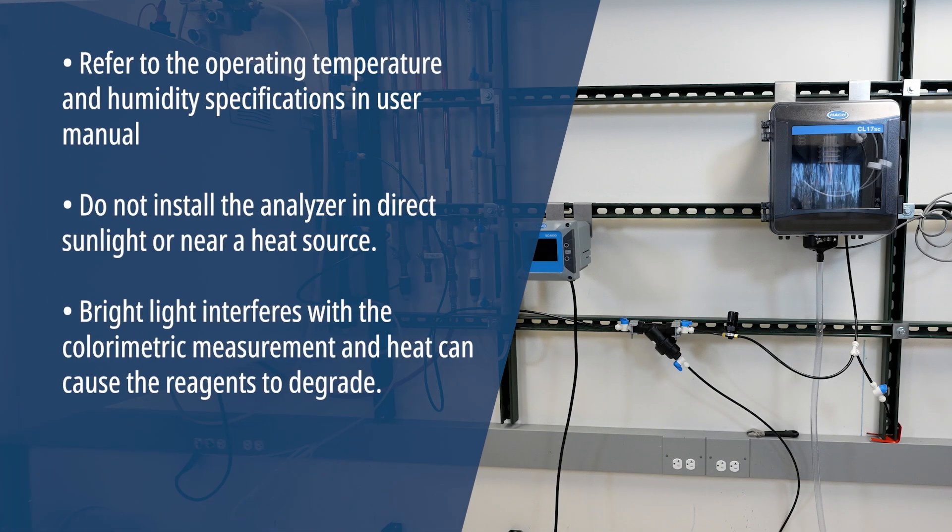Install the analyzer indoors in an environment with minimum vibration. Bright light interferes with colorimetric measurement, and heat can cause reagents to degrade.